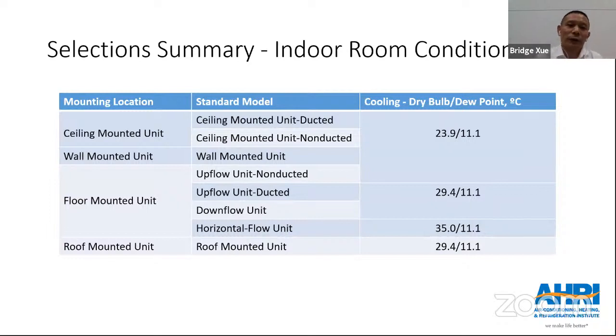Let's talk about room air conditioning. So from the configuration, for different configurations, right? For the ceiling mounted unit, condition one, which is 23.9 dry bulb and 11.1, were applied. For the floor mounted, they have two different conditions. Condition two, 29.4 dry bulb, and the 11.1 dew point will be applied. For condition three, 35.0 dry bulb and 11.1 dew point will be applied. And for the roof mounted unit, which is a new configuration, we added this in the standard just last year. So condition two will apply.